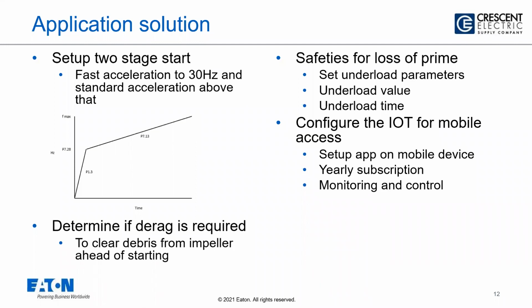And if there is a derag, sometimes you are stuck with large debris, and in order to clear the debris, you can configure the drive to do a derag function. At the start it can just reverse and then start, so it clears the debris, or during the running you can configure it so that whenever it gets stuck and stalls due to debris, it can reverse and then restart. That derag function is part of the drive feature.